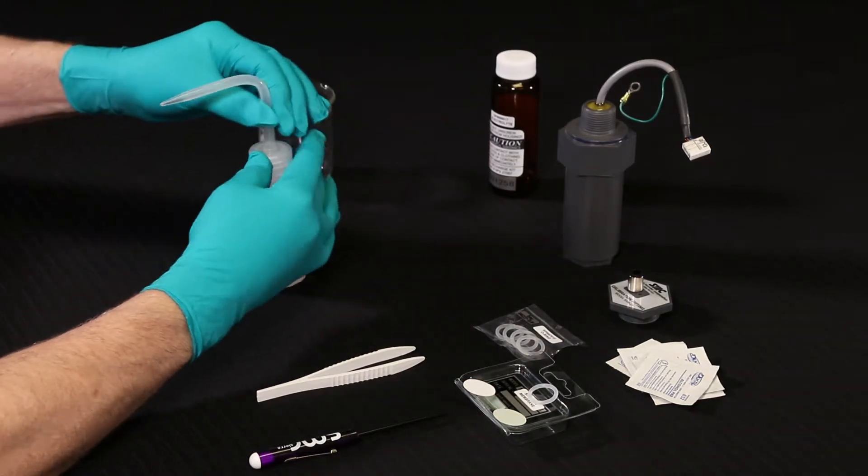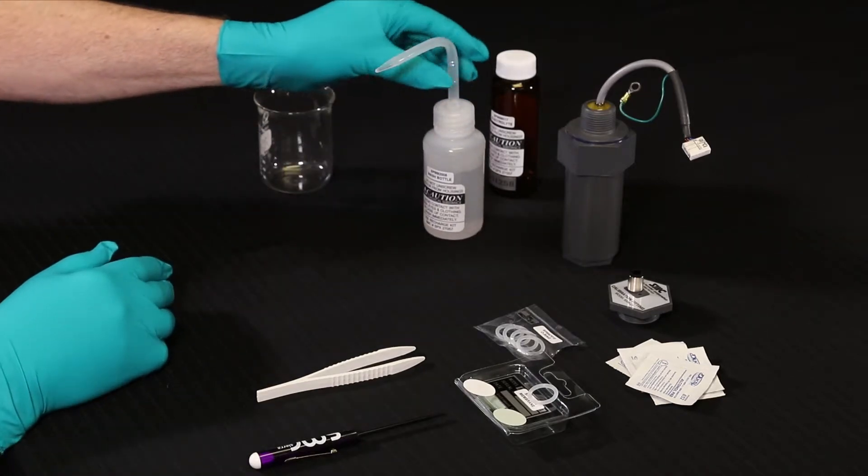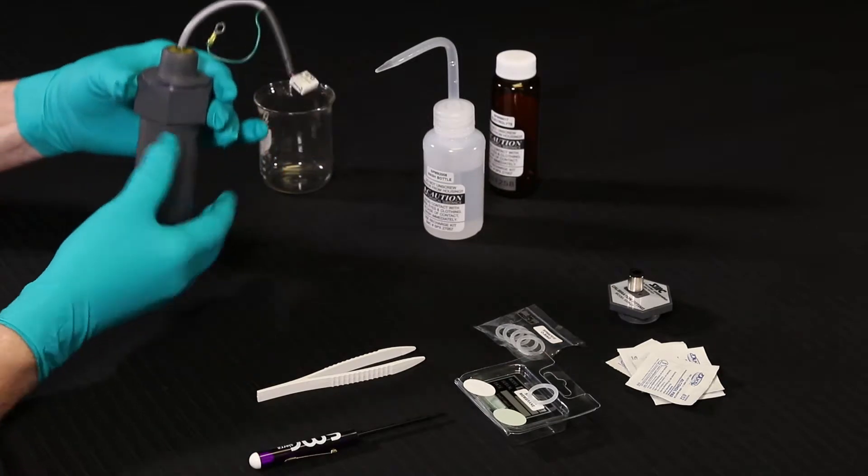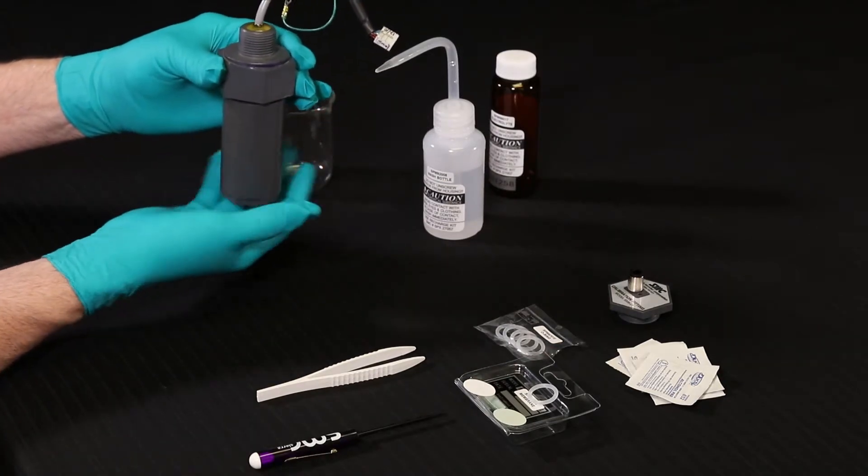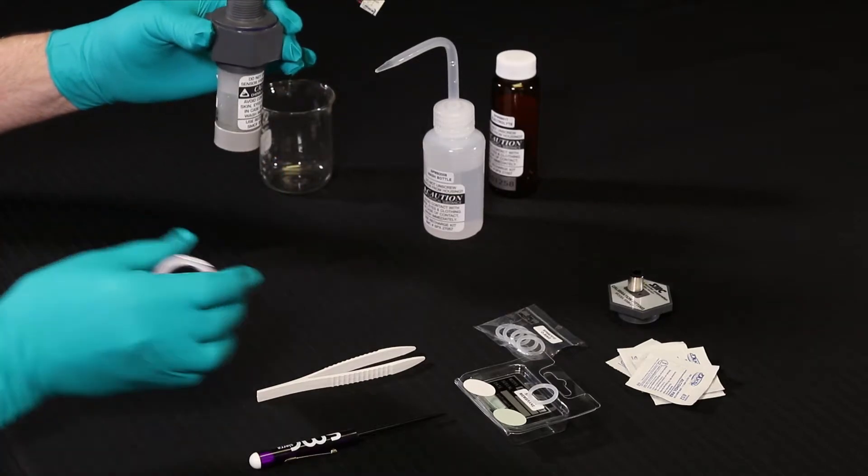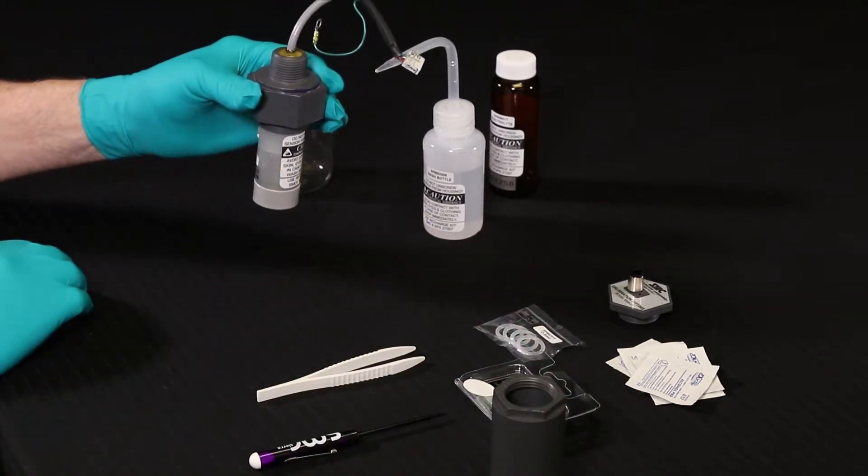Next, unplug the sensor assembly from the transmitter and remove from the enclosure. Next, unscrew to remove the outside protective gray barrel from the sensor assembly. Do not attempt to unscrew or disconnect the glued sensor cell from the upper sensor housing.